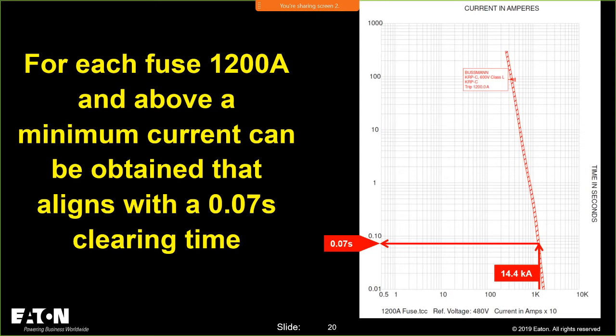Every curve, this is what I call the resume of an overcurrent protective device, because it shows you how it's going to perform whenever you put current through it. So this particular 1200 amp fuse establishes a clearing time of 0.07 seconds for any current greater than 14,400 amps.